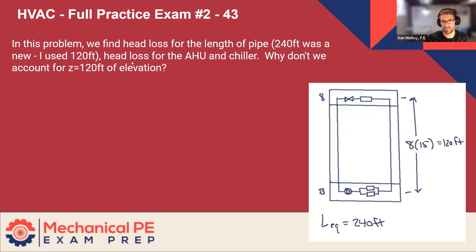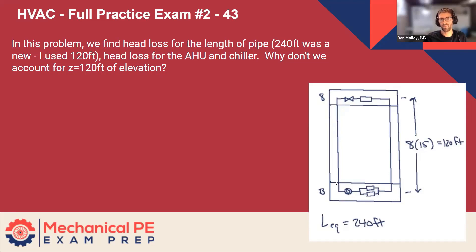I used 120 feet head loss for the AHU and chiller. Why don't we account for Z equals 120 feet of elevation? So the question was, what's the head added by the pump? Anybody have any ideas here? Why don't we account for Z equals 120 feet of elevation? You can unmute and just shout it out or type it in the chat. Or maybe you think we should account for the 120, in which case I'd like to hear the arguments.